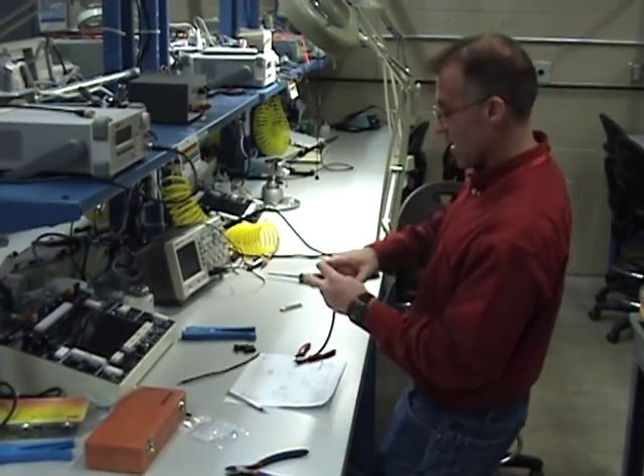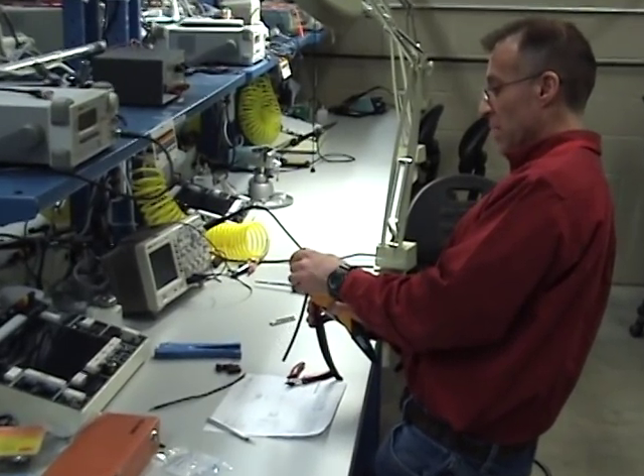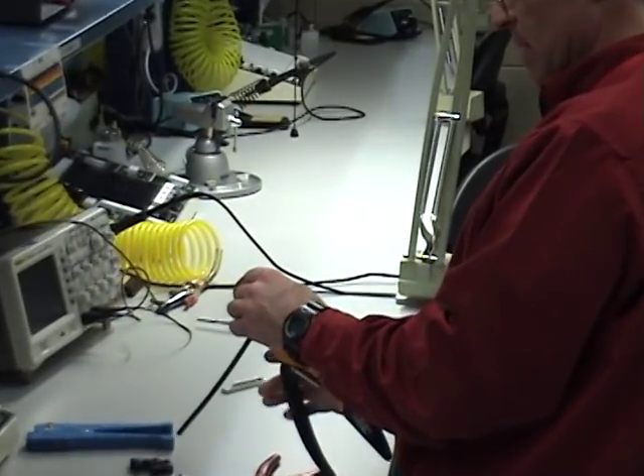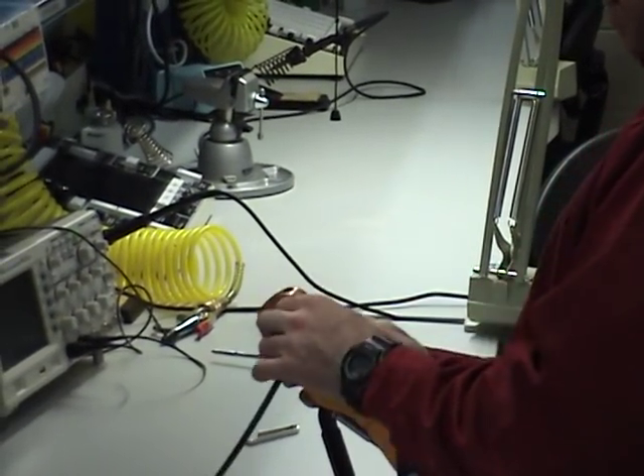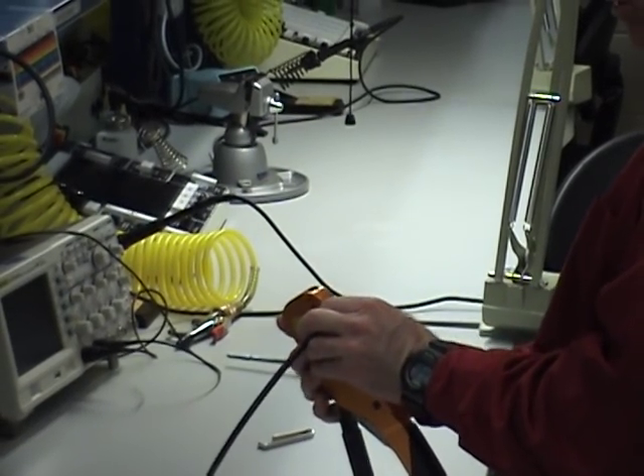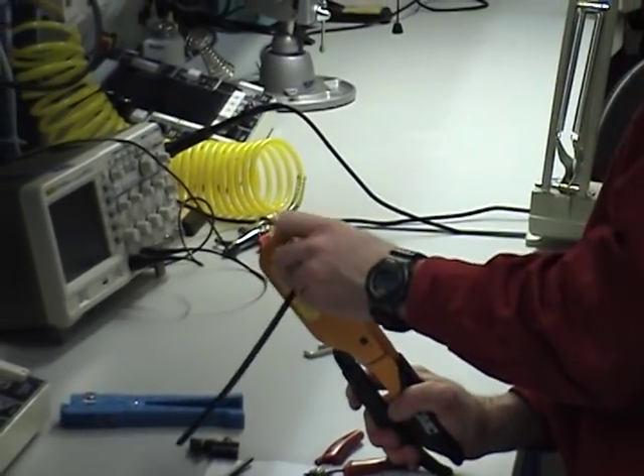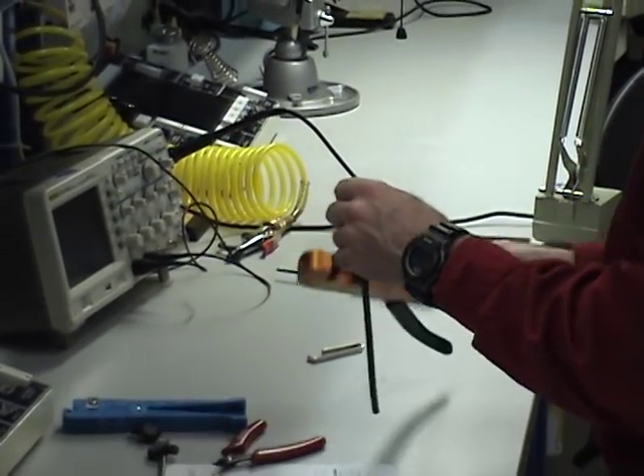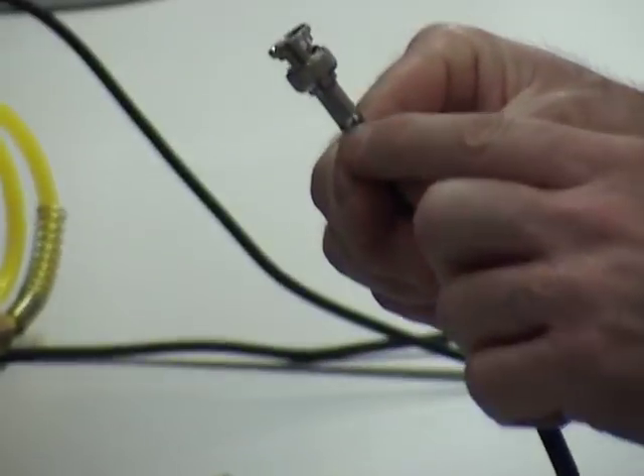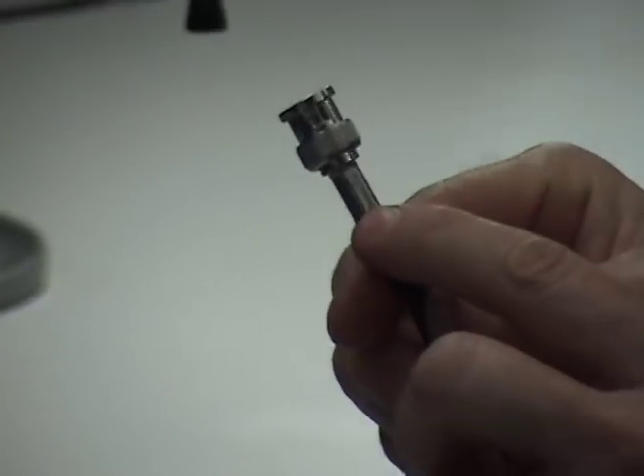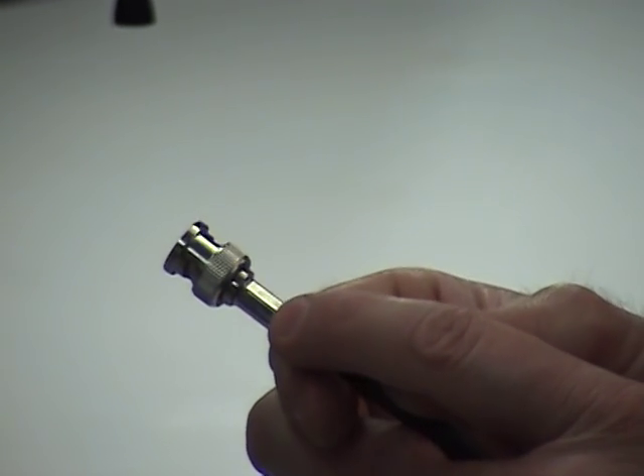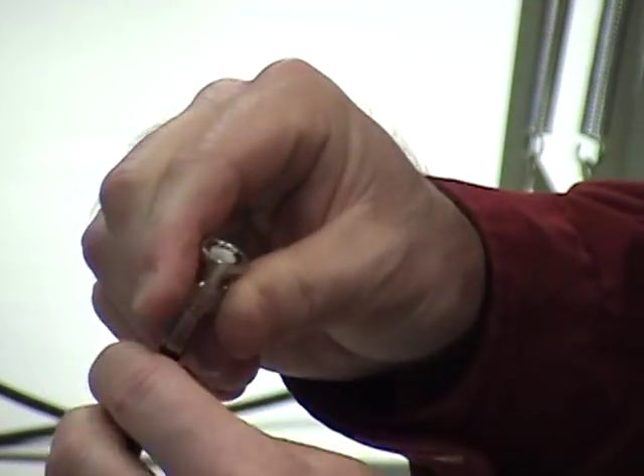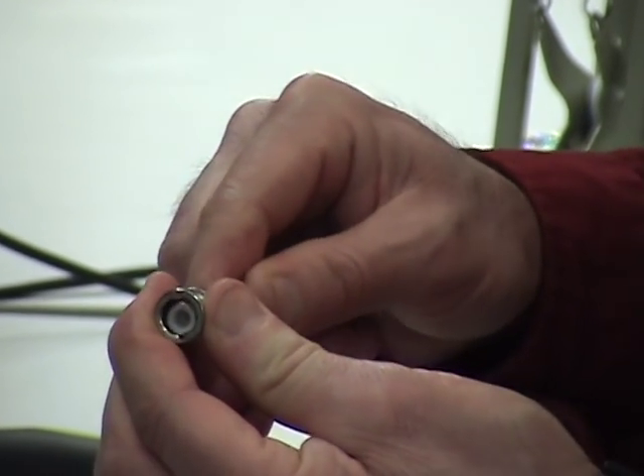Now I'm going to look at my pin to make sure that didn't slide out. I'm still flush with the top, still good there. I'm going to hold them all together and just use the table to get it started. And it's trying to slide on me just like that. So I'm going to use my fingernail and hold it. Hold it and crimp. Crimp, tug test. I'm going to look here. Look at my crimp went all the way around. Looks like a very good crimp. I didn't over crimp it and it didn't under crimp it. It doesn't spin. Tug test. My pin is all the way flush with the top. That's a good connection.